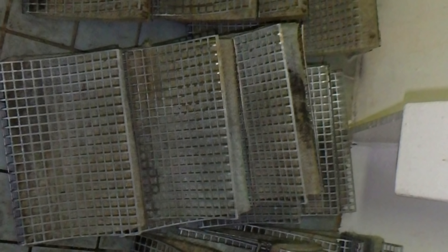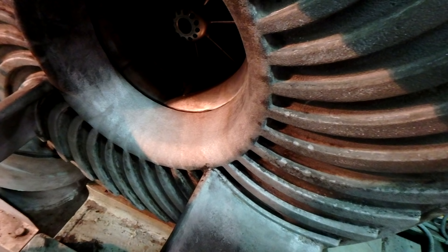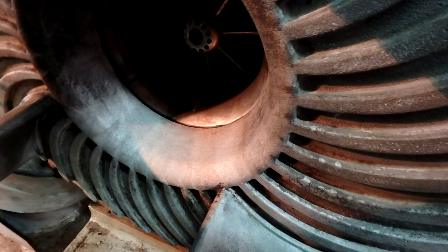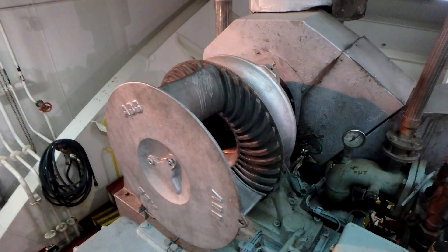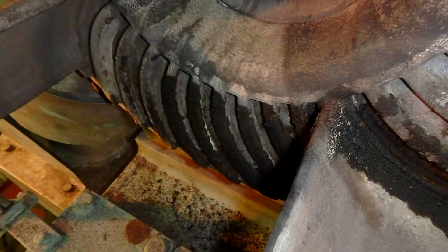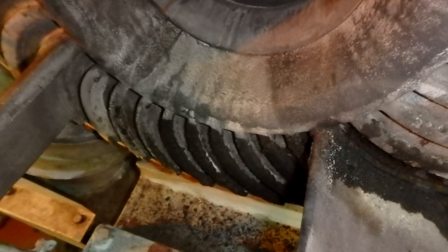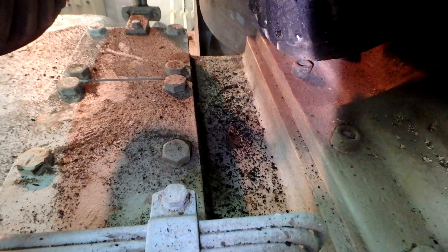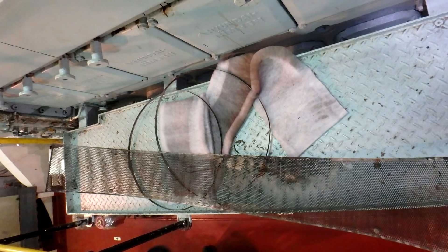Always place the original filter on top of the silencer. As I have seen in most engine rooms, they use a white cover for the turbocharger filter, but this is not proper — the design is different. We must use original spare parts as much as possible. We also inspected number 3 diesel generator, and in the bottom we found some dust accumulated, but there was no trace of heavy damage on the wheel — it was only black colored. This dust accumulation is the reason we need to put a proper filter.